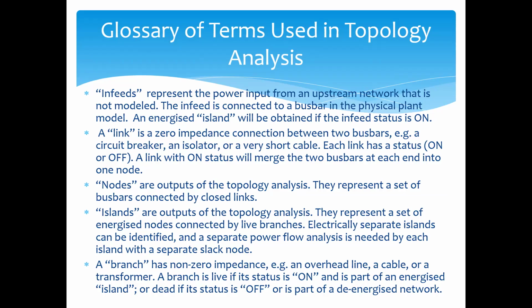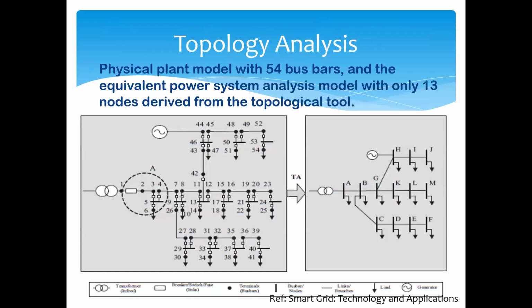A link means zero impedance connection between two bus bars. What does it mean? It may be a circuit breaker, or an isolator, or a very short cable. Each link has a status on or off. A circuit breaker can be off or on. A link with on state will merge the two bus bars at each end into one node. If the link is on, the two bus bars become one node. If you remember the previous one, here, if the circuit breaker is on, these two become one node.